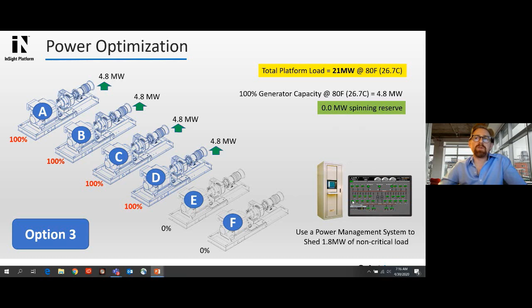So if we're looking at the total plant load, here we're looking at a year's worth of data. Looking at the 6 engines that are on there, the gray indicates the power capacity of the 6 engines across the temperature profile. So with 6 engines in operation, this customer would never have any deficit, and would be able to meet the power demands.